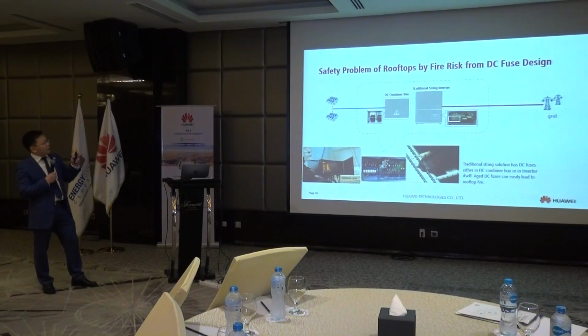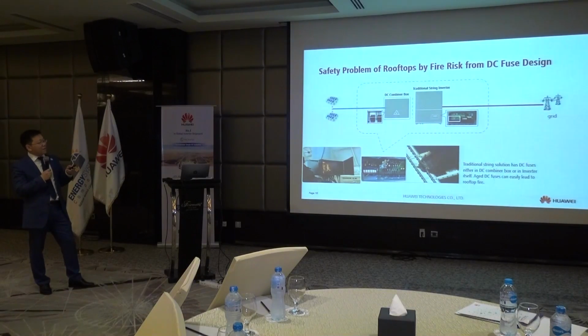Another issue is safety, since rooftop projects are mainly focused on safety, which is the top priority for all projects. The big difference between us and other solutions is that we don't use DC combiner boxes to combine all the strings. All strings connect to our inverters directly, so we have fewer DC paths and DC loads, meaning less DC arcing risk, which means less fire risk. So we can ensure high safety.